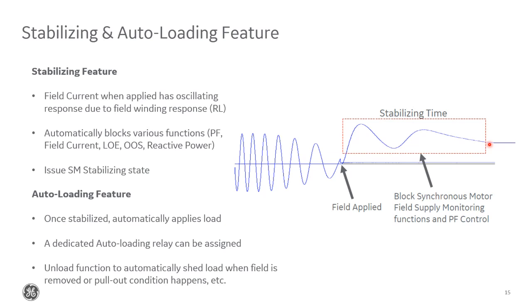And if you choose, you can assign a relay output and use the built-in auto loading feature to automatically close this output and trigger application of the load. With this, if you choose to do it this way, we can also automatically shed the load if we see the field has been removed or if the motor pulls out of sync.